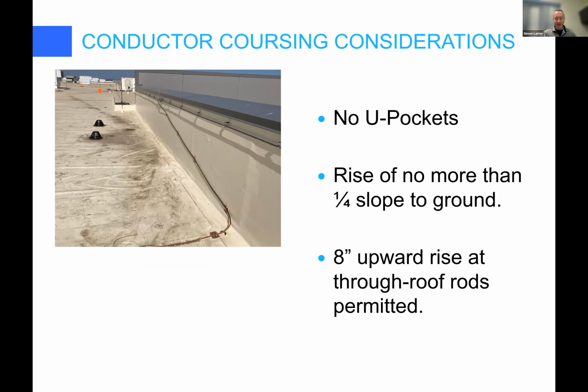U-pocket. You see this a lot sometimes. A U-pocket is when you bring the cable down, you come over and you go back up again. We're not allowed to do that. We want to make sure that the lightning protection conductor runs horizontally or downward to ground in all locations.